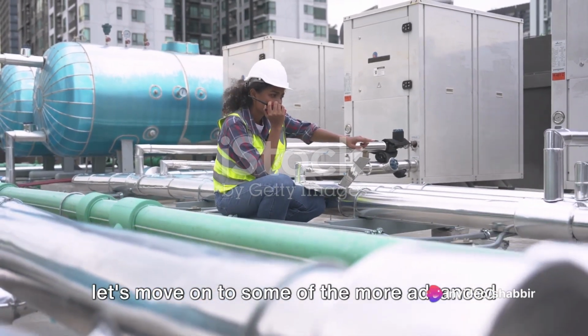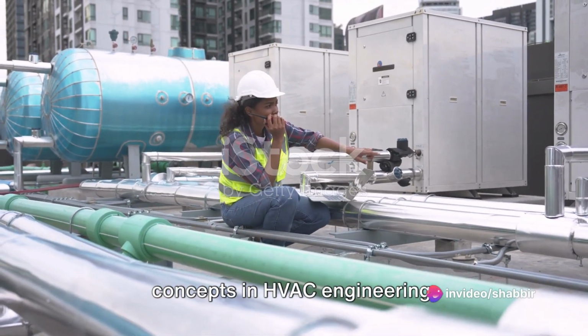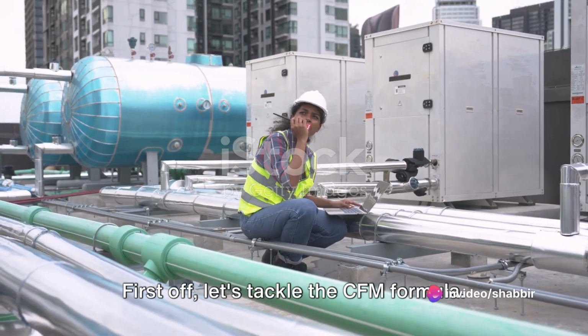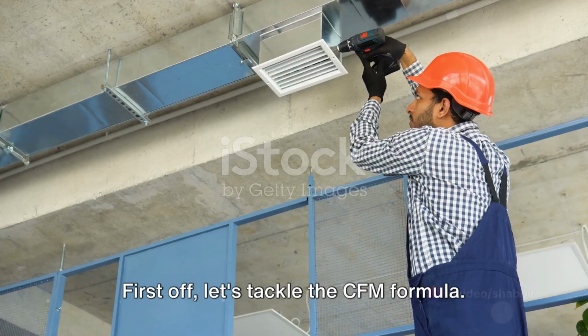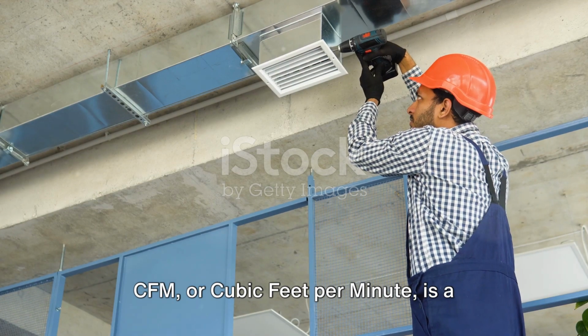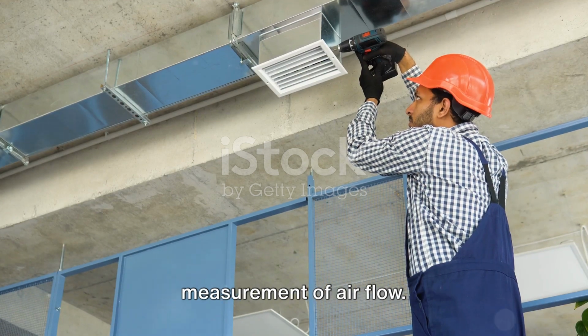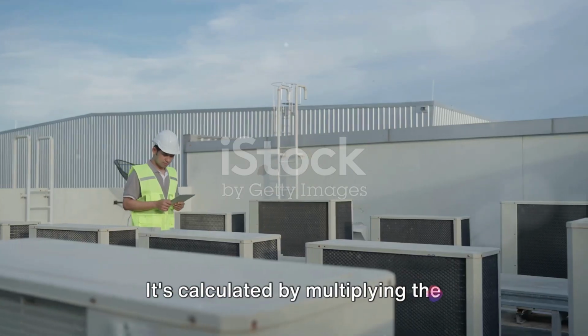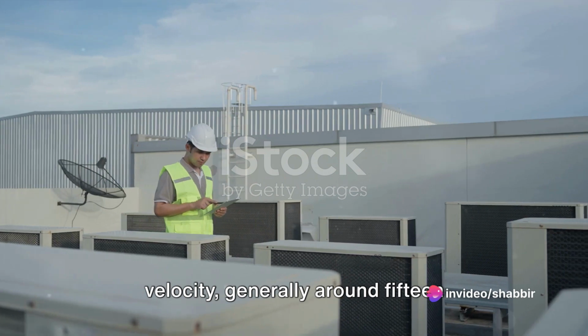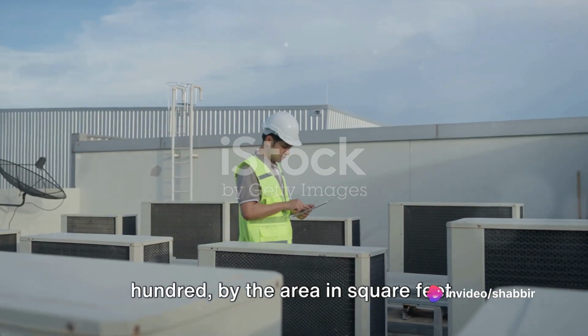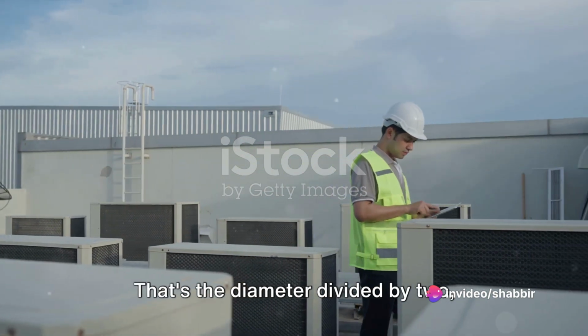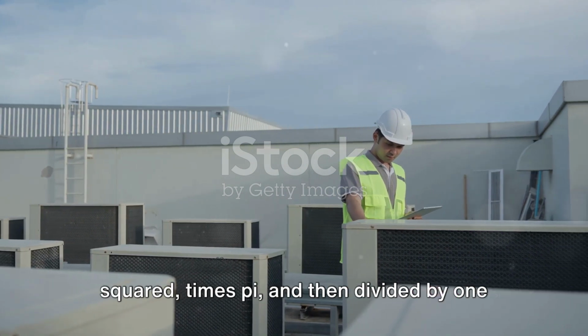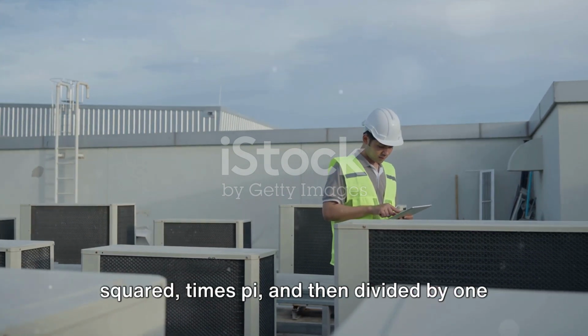Now that we're familiar with the basics, let's move on to some of the more advanced concepts in HVAC engineering. First off, let's tackle the CFM formula. CFM, or cubic feet per minute, is a measurement of airflow. It's calculated by multiplying the velocity, generally around 1500, by the area in square feet. That's the diameter divided by 2 squared times pi, and then divided by 144.